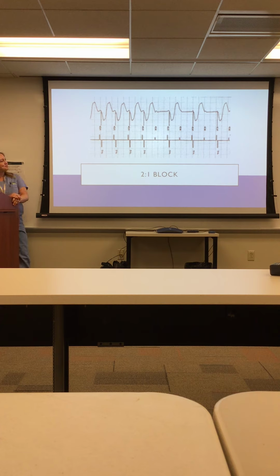I would say with younger patients we'll see this, maybe in their 40s, that their rates can get up higher, and if their device is programmed at say 120, and they go to exercise or work out and they get up into the 140s, they're gonna see this, because if they're dependent on their pacemaker and they count on that 1-to-1 tracked beat, once it gets past the 130 mark, that's when it's cut in half. Okay. Yeah, because the pacemaker is going to say, no, this is too fast, I'm not supposed to track this high. So then that's when it will back off, which in this case isn't good for the patient, but it's also something that we don't want, to track high atrial rates either. We can't live with that fast of a rate all the time.